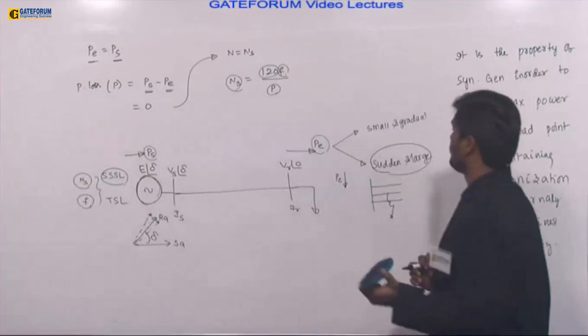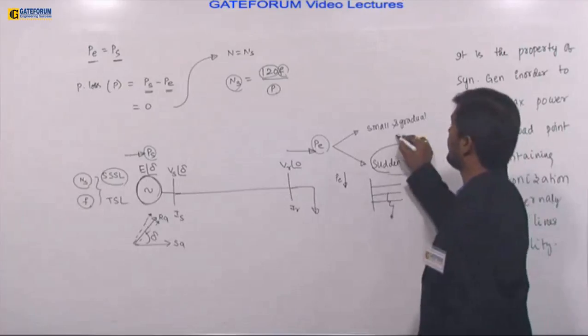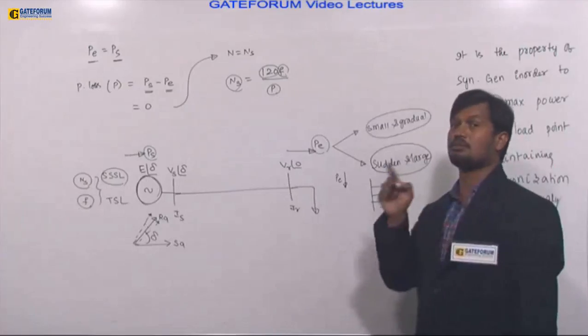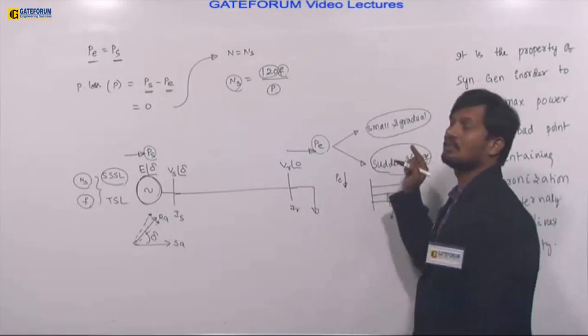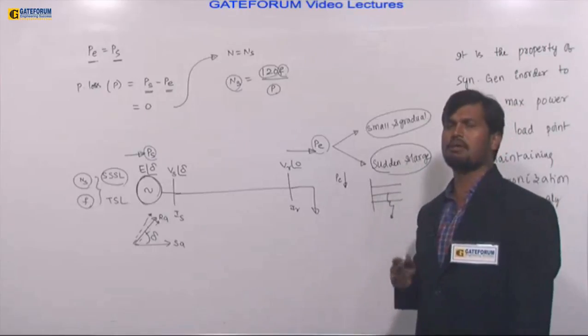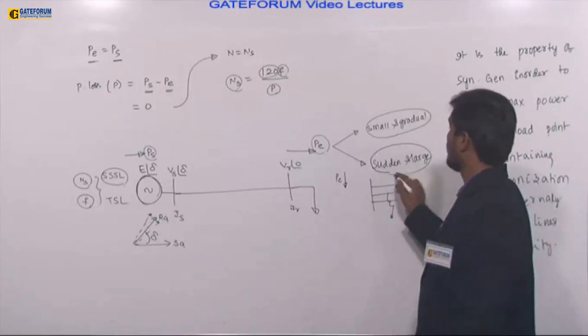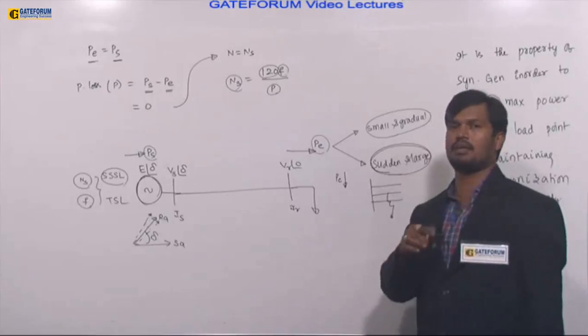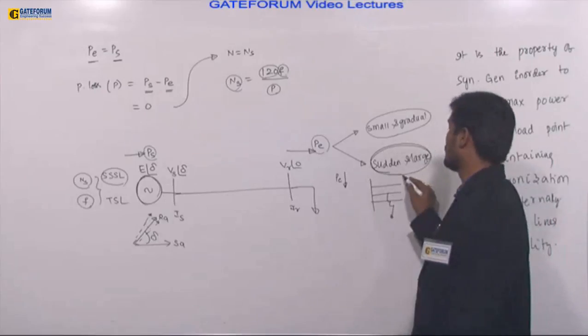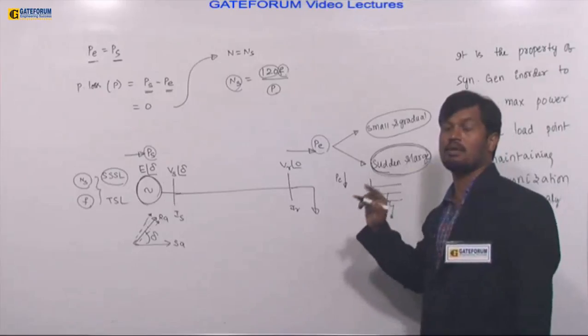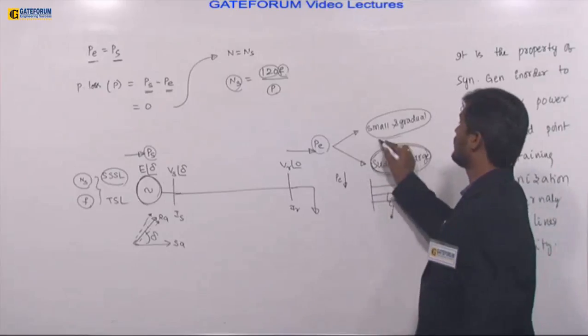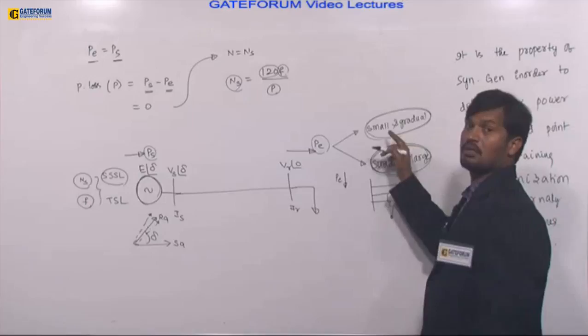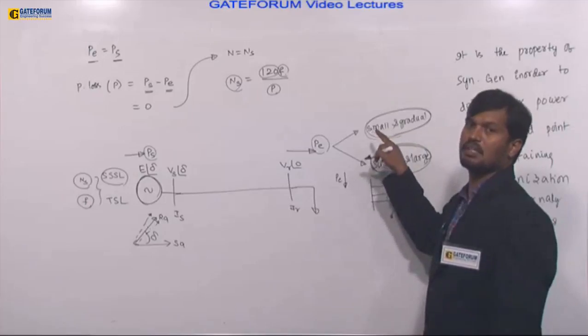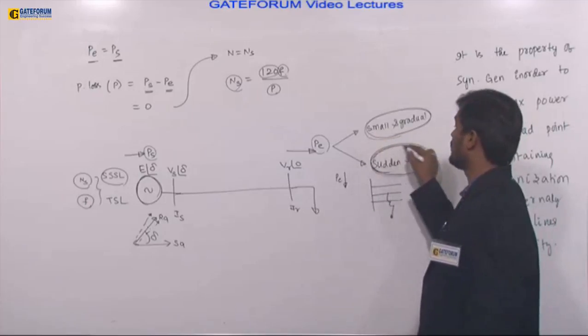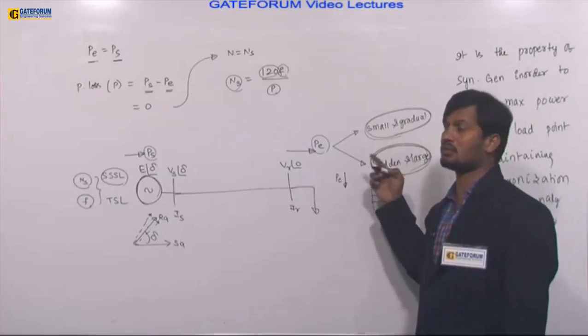Now tell me, is small and gradual variation of load more common, or is sudden and large variation of load more common? Small and gradual variation of load is more common but less severe; it doesn't affect the system, but it occurs every day. Sudden and large variation of load is less common, but when it occurs, the power system can go down. Therefore, such faults are rare but most severe.